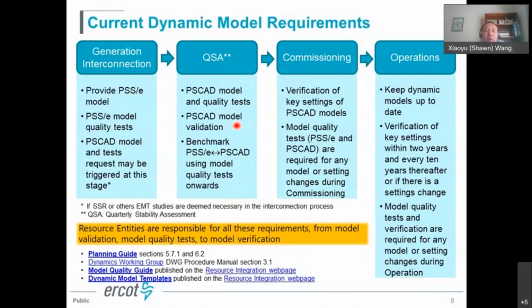Also, the PSCAD model unit model validation report needs to be provided. This report benchmarks the PSCAD model result against the lab test, so that we can make sure the PSCAD model accuracy reflects the actual devices.